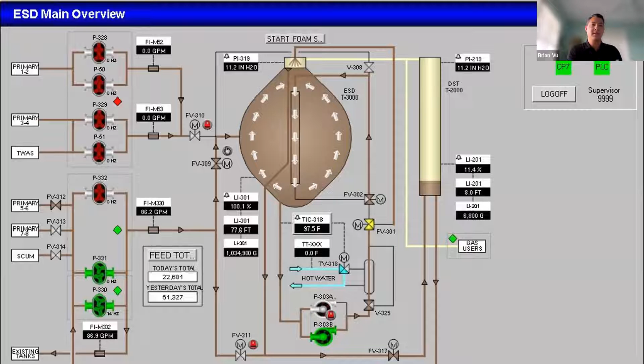We got valves that we can operate over here on this left-hand side to switch from primary tank to primary tank with sludge pumping. We can remotely control and automate pumps when they come on and off. We can visually see what pressures are happening within the tank, changing automated valves to change mixing cycles within the tank, temperature readings to send back the signals when we heat and when we don't heat. So this kind of gives you an idea of how you can apply automation on a highly complex system like this that makes it fairly simple to operate.